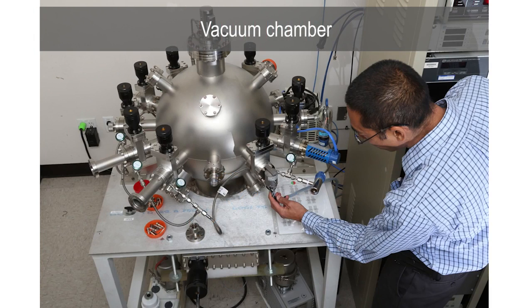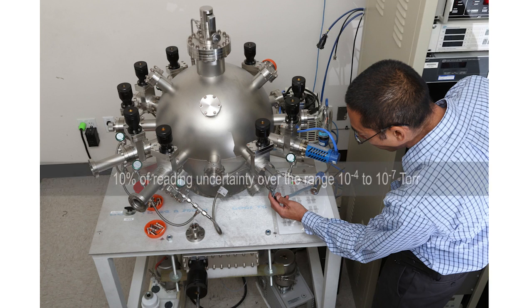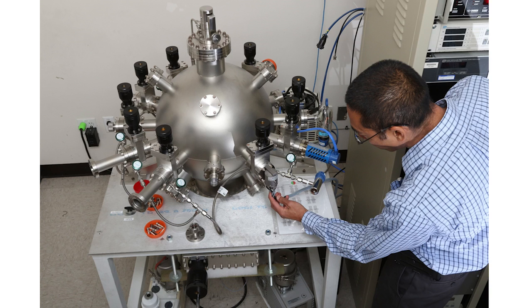This is the vacuum chamber that was built by one of our folks in El Segundo, Glenn Gaza, for measuring ionization gauges. Over the range of 10 to the minus 4 torr to 10 to the minus 7 torr, the uncertainty is well under 10%. So if you have ionization gauges and you would like to have those measured accurately, this may be a capability that we can do for you.